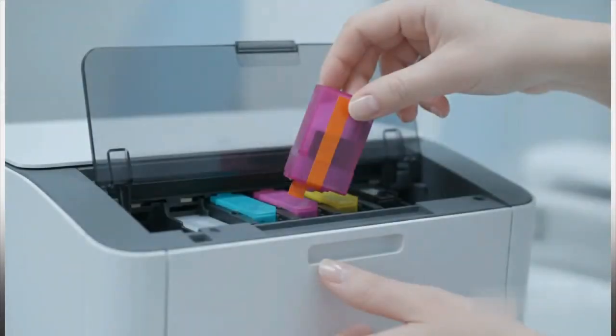Many E0 errors happen because cartridges are not installed properly. Open the cartridge access door and remove each cartridge carefully. Verify that all protective plastic tape has been removed from every cartridge. Then, reinsert every cartridge firmly until it clicks into place and close the cover. Remember, never touch the copper electrical contacts on the cartridge.